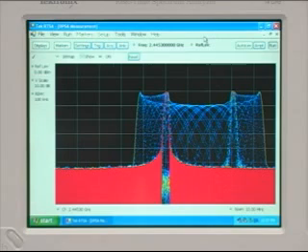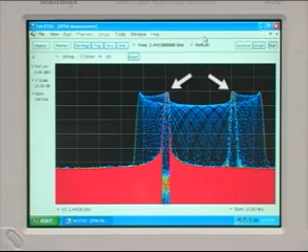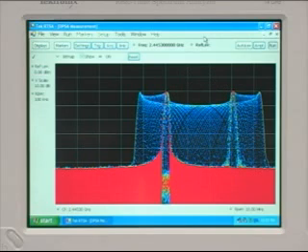DPX technology offers the best solution for discovering transient RF signals caused by glitches. We can see here that there are two specific frequencies, and there is undershoot and overshoot when the signal hops between the two frequencies.